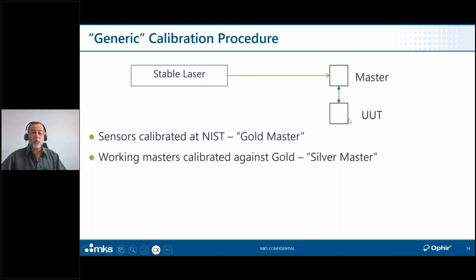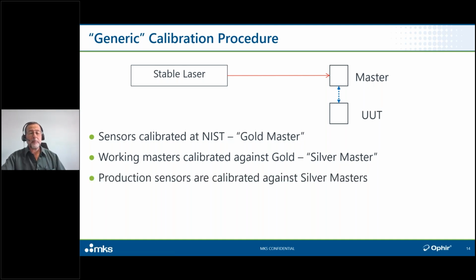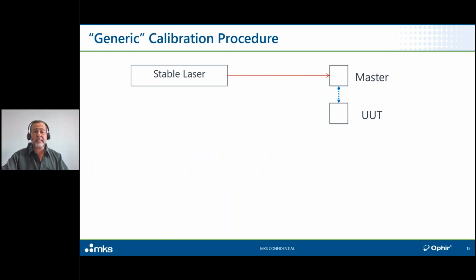Then we measure with the unit under test, the sensor being calibrated, and then we adjust it, as we said before, strictly speaking. Okay, now we can forget about that bit. We adjust it so that it reads as close as possible to the master, and it has now been calibrated. And the sensors that finish production or that get sent by customers to us for their annual recalibration get calibrated against these silver masters. If it's a thermal sensor being used for single shot energy measurement, there's an additional step.